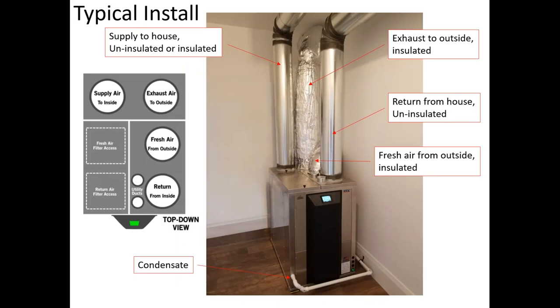This is a picture of a typical installation. You can see the external ducts are insulated and the internal ducts going to and from the house are uninsulated. There's the condensate line, and the system just plugs into a 120 outlet, so a 15 amp breaker is sufficient to operate it. The top view on the left side just shows the duct configuration. The utility ducts shown are no longer present. Those are now incorporated into the standard return ducts. And filter access is from the top, so the return air filter and fresh air filter are both accessed through this top panel.